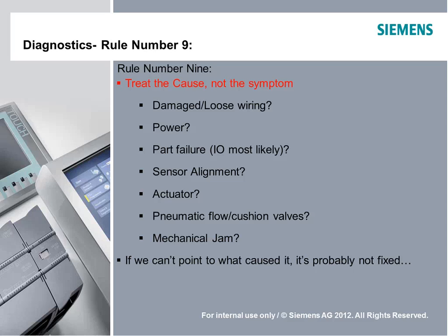And lastly, if you can't point to what caused the problem, it's probably not fixed. Too often we actually go out there and move things around a little bit, and it starts working again. You're not real sure what actually fixed it, and it started running, and it seems to be doing just fine. But boy, I'll tell you, those are the ones that are likely to come back and bite you, because unless you're pretty sure about what it was that caused the problem, it's probably not fixed.